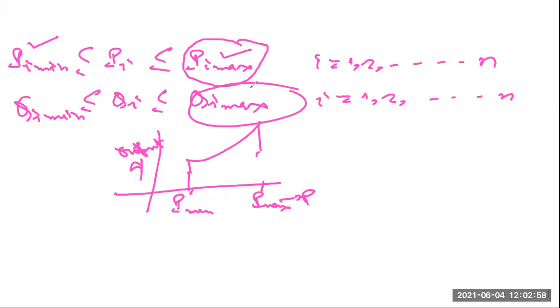And similarly this Qi min, again why we cannot go below this particular limit. That is because of the limitation that the boiler cannot sustain that particular flame, and the turbine does not have a sufficient amount of heat. The steam will not be at the superheated condition, and then the problem will come, that is, the turbine blade gets corroded. So this is the basic reason why we cannot generate below the minimum active power limits.